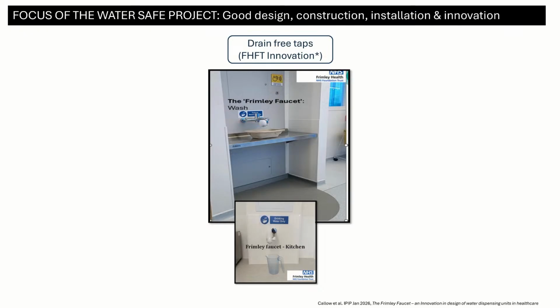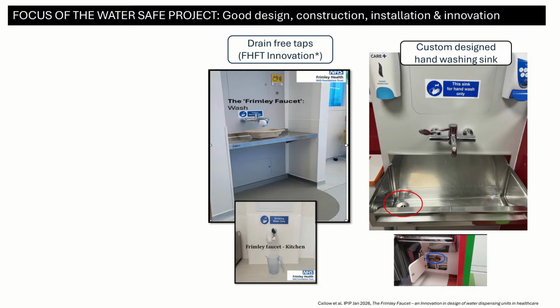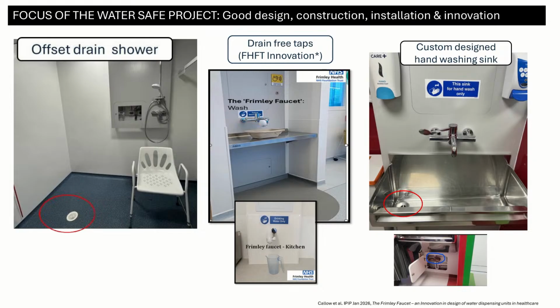And this is the similar type of water that we use in the kitchens as well, where we have a pressure operated tap where you can get sterilizing grade water through these outlets. So it's also sustainable, and this is why this approach has been used in our trust. And then again, these are design aspects that we've incorporated into hand wash basins. This is a custom made sink where the drain is offset, and there are no nooks around the drainage system itself where bacteria can hide and increase the splashing risk.